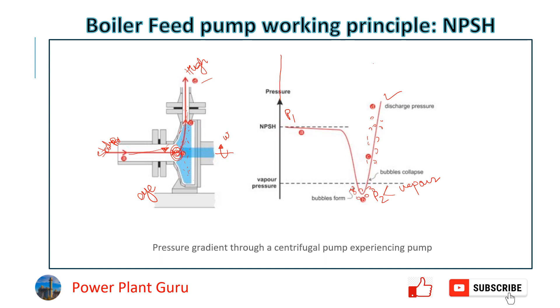The alternative to eliminate this pitting is to increase the inlet pressure — instead of P1, you raise it to P1 dash. If you increase this inlet pressure at the boiler feed pump, the pressure will still fall at the impeller eye but it will not fall below the vapor pressure — there will be a sufficient margin. So P2 dash is higher than the vapor pressure, cavitation does not happen, and the equipment is safe.